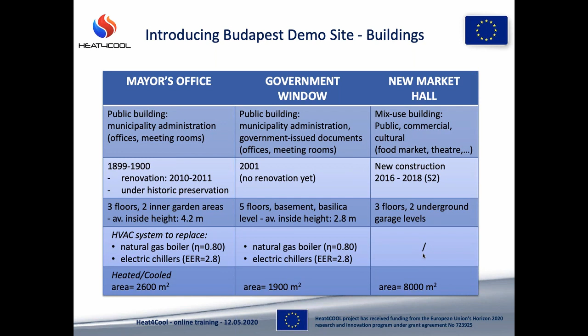Looking at the layout of the system we designed: there's a heating central with wastewater screening, heat exchangers and heat pumps on the side, as I've shown before. Here we produce in our heat exchangers the closed loop clean water that can feed the heat pump. But for better efficiency in heat transport, we put another heat pump into the market hall, which is a big consumer in the system. So we have two heat pumps - one in the big heating and cooling center, and the other under the new market hall.